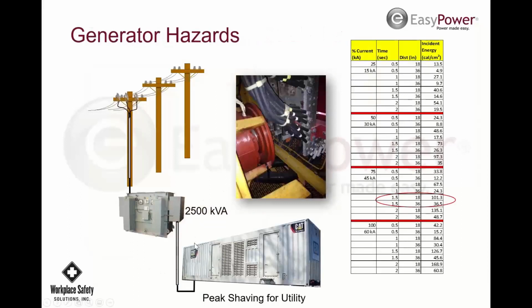Now, what can we do differently here? I tell the Cat dealers, because this happens a lot with the utilities, they're all over the place, and I work a lot with Cat dealers around the country. But I said, bring in a fuse disconnect on a skid or a pallet or however you want to rent it, and just set it up so that there's a fuse disconnect here, so they have a lockout tagout point that they can use. Plus, it's going to bring down the arc flash level significantly by having a fused disconnect. So a lot of them are doing that now.